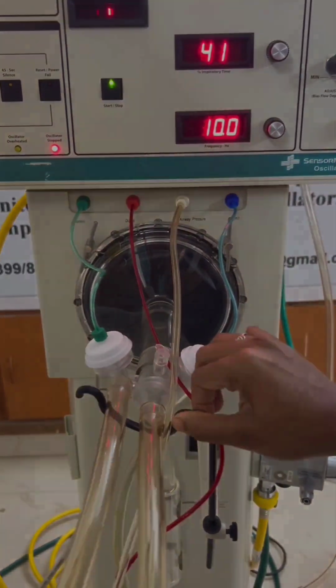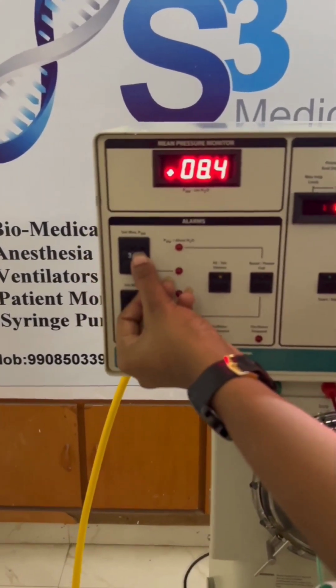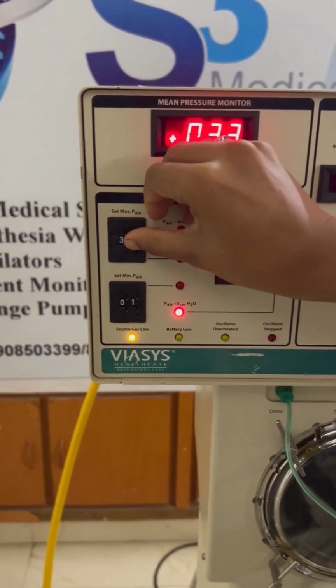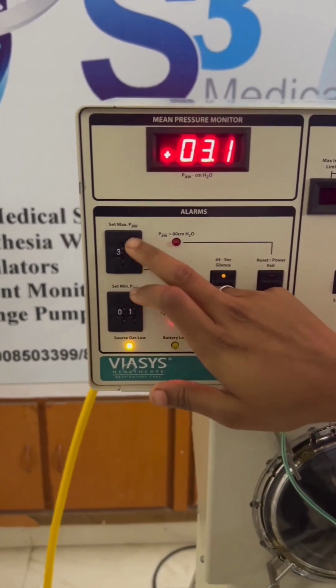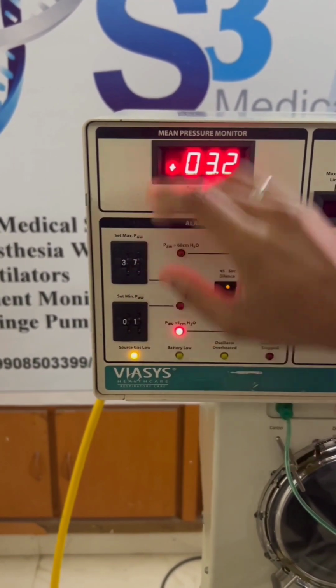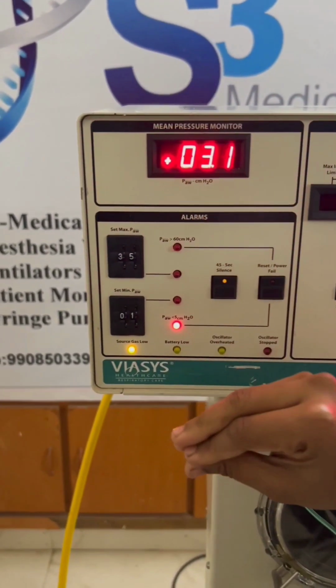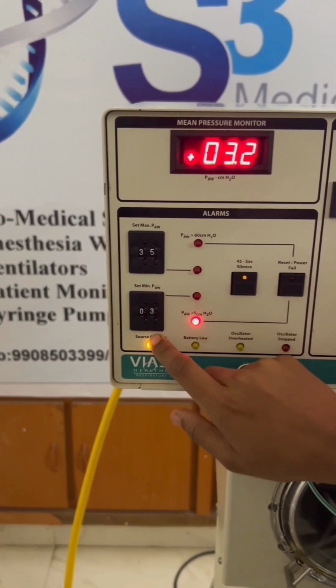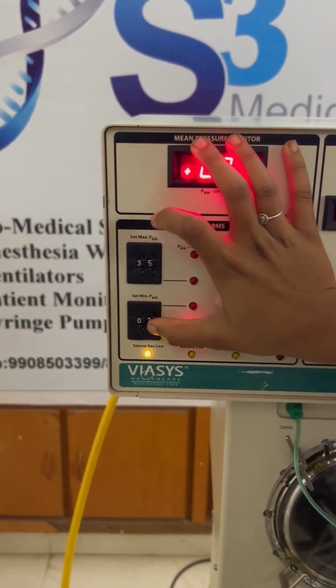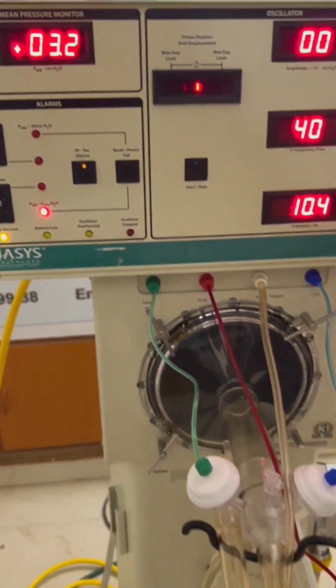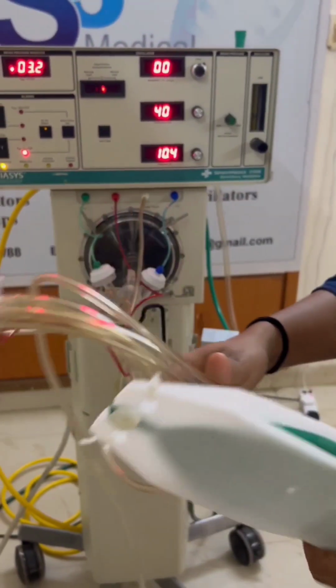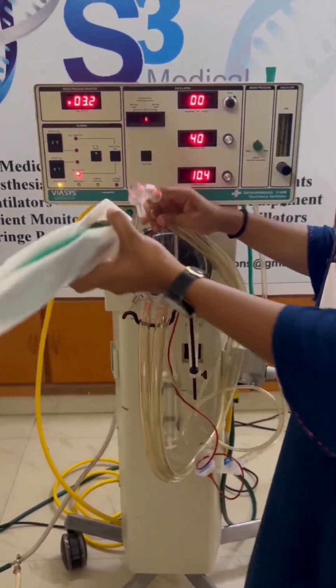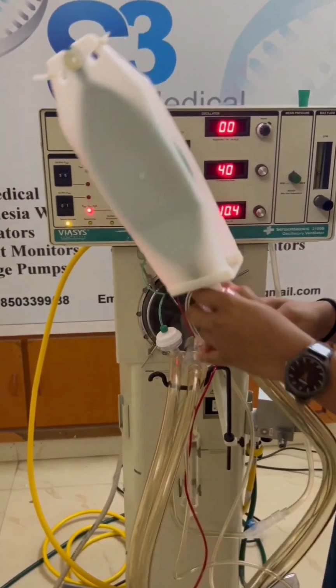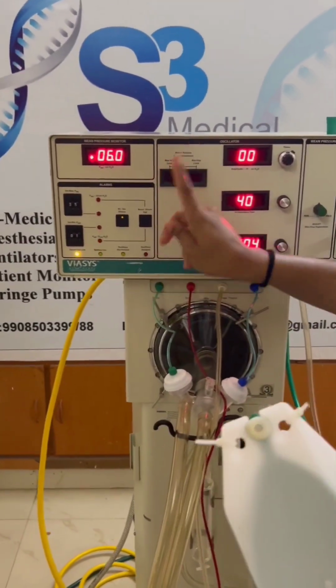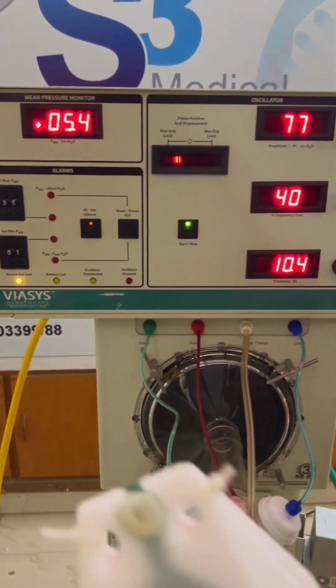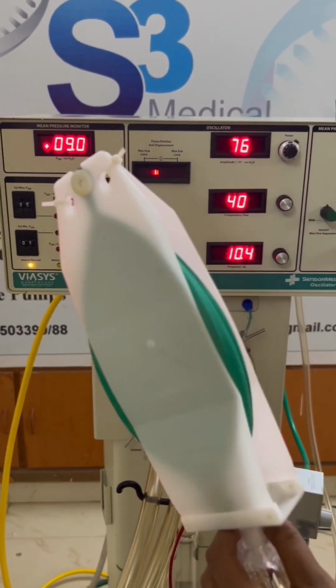And these are the alarm settings for the pressure, set max pressure and set min pressure. Here you can adjust the knobs by rotating. We need to fix 5, and here also you can rotate it. We are setting to 1. Now we're going to connect the test lung. Reset. Before giving start, we need to set reset and then start ventilation. Now it is ready to give ventilation to the patient.